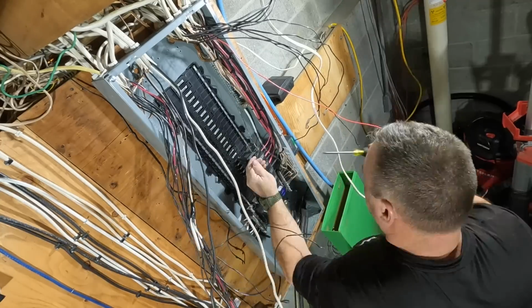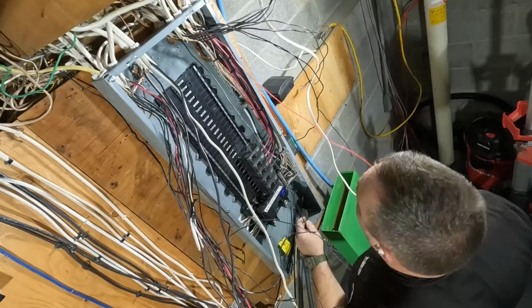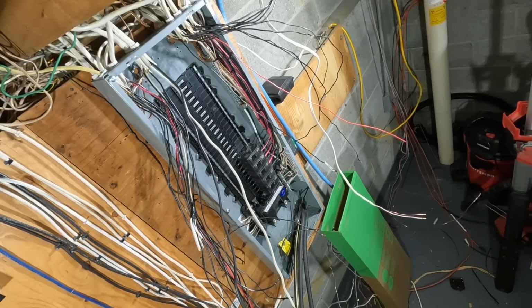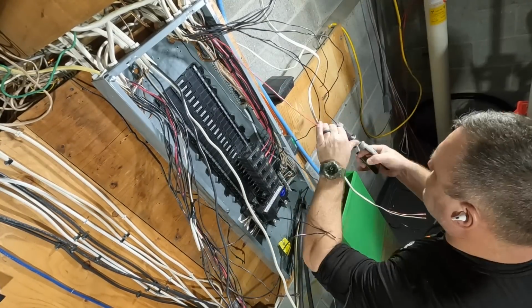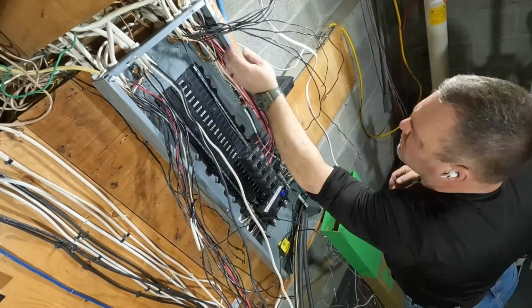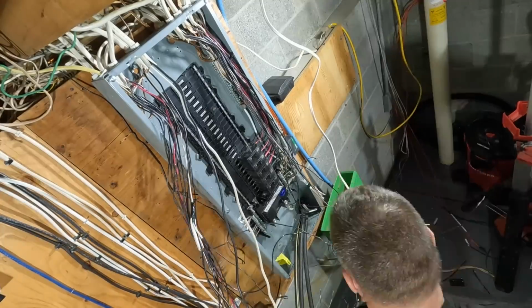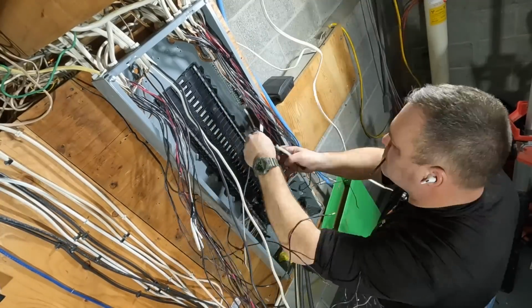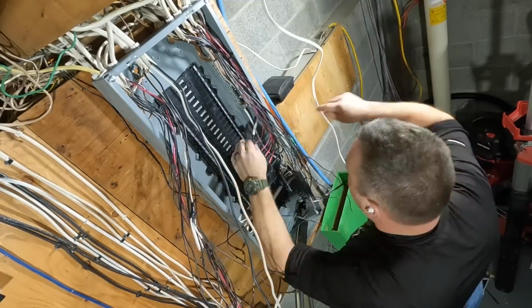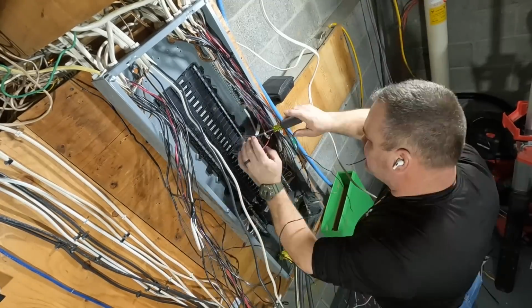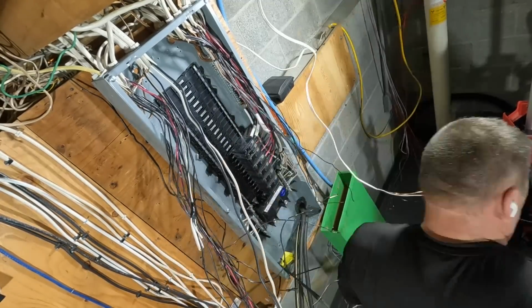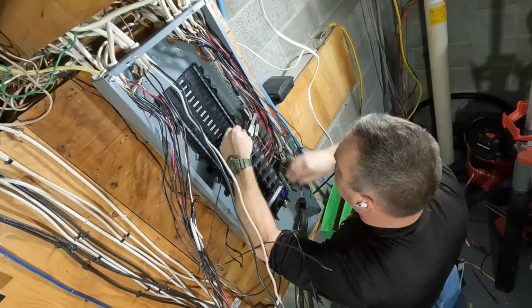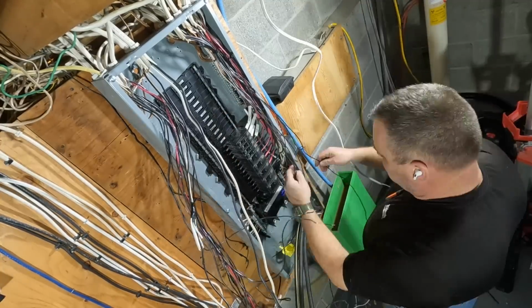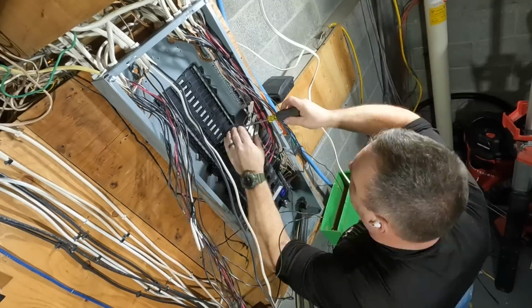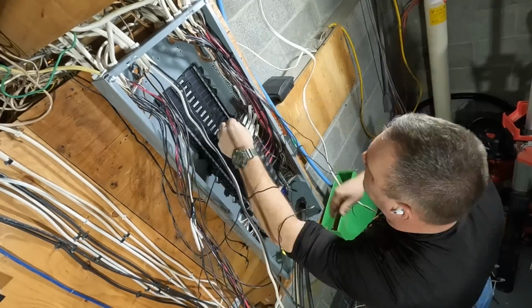With QO, there's a specific place they want you to put the surge protection on the bus bar, and that's closest to the main breaker. The other brands, such as Cutler-Hammer BR, do not require that they be closest to the main circuit breaker. So I know I've been over this before in the comment section, but if you know why QO requires that breaker to be closest to the main breaker, let me know in the comments. Because with BR, we don't need to do that.